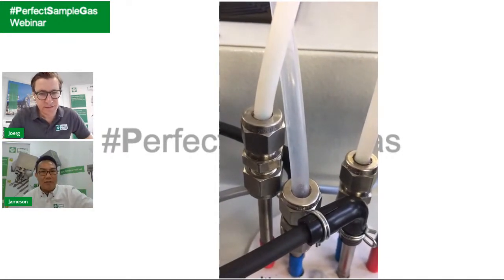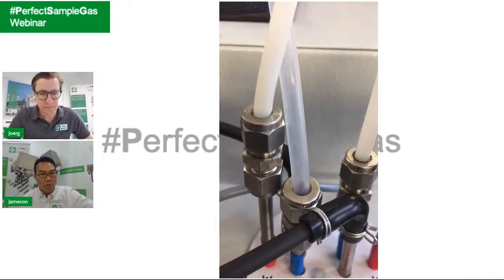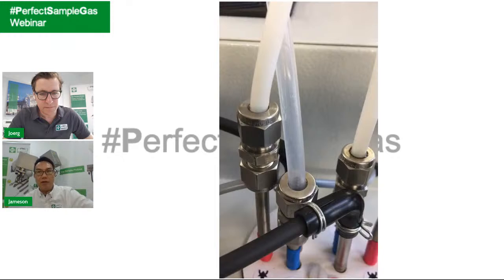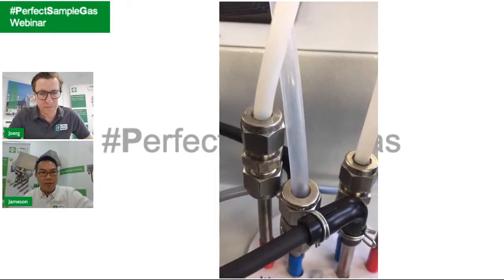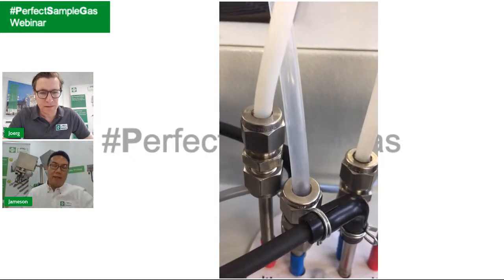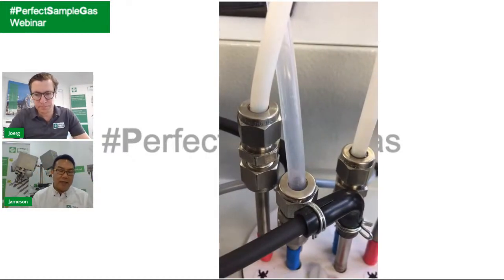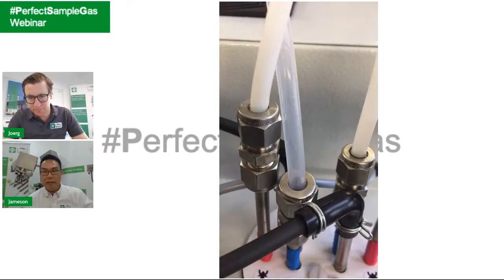Yeah, there are several reasons why the cooler outlet is supposed to be dry. It's supposed to be dry at 3 degrees C after cooling. What really happens is that at the point of inlet, many people have the heated line at 180 degrees. It is heated all the way onto the analyzer cabinet, enters the analyzer cabinet, and stops there. Then the tubing, naked tubing, is unheated, maybe as long as 1 meter, and then it goes back all the way to the cooler. That defeats the whole purpose of holding the temperature. This 1 meter length actually loses all the heat.